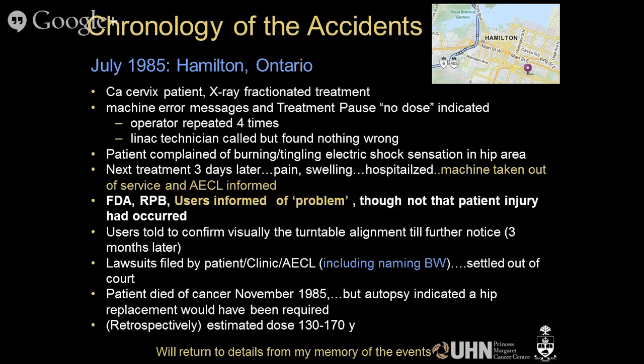There was nothing wrong, but the patient complained of burning and tingling, like an electric shock sensation in her hip. And then 3 days later she came with significant symptoms. The machine was taken out of service. AECL were informed. The FDA, the Canadian Radiation Protection Bureau, and other users were informed, although in retrospect, it may have been that they were not told the patient's injury had occurred. And users were told to confirm visually that the turntable was in the correct position until further notice. There were lawsuits, including one naming me, for reasons that were obscure to me at least. But it was a generic lawsuit with suits and countersuits. It was all settled out of court.